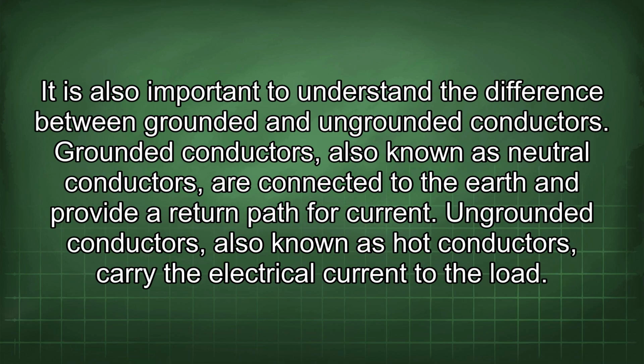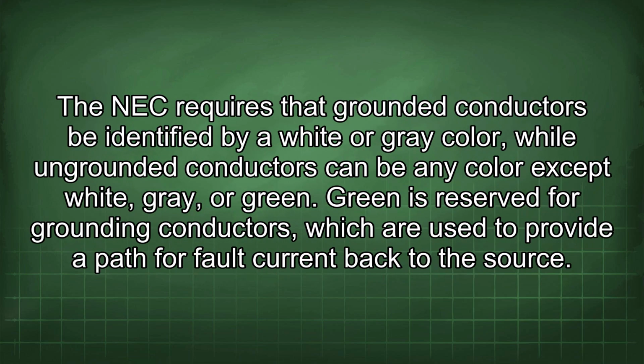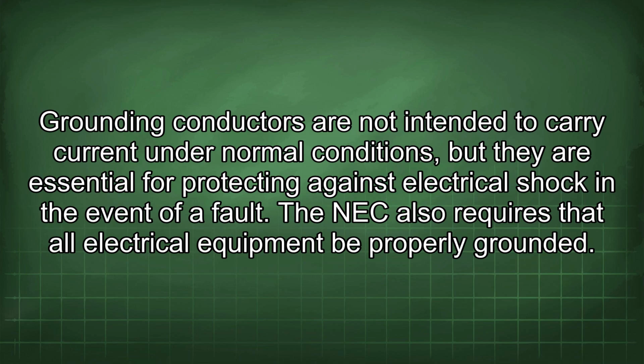It is also important to understand the difference between grounded and ungrounded conductors. Grounded conductors, also known as neutral conductors, are connected to the earth and provide a return path for current. Ungrounded conductors, also known as hot conductors, carry the electrical current to the load. The NEC requires that grounded conductors be identified by a white or grey colour, while ungrounded conductors can be any colour except white, grey, or green. Green is reserved for grounding conductors, which are used to provide a path for fault current back to the source. Grounding conductors are not intended to carry current under normal conditions, but they are essential for protecting against electrical shock in the event of a fault.